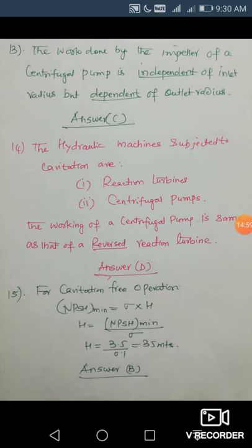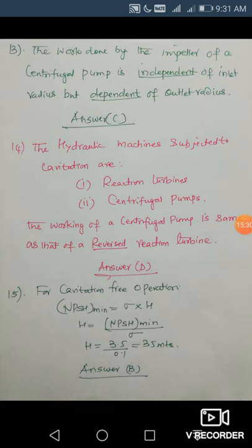For the last question: for cavitation-free operation, NPSH_min = σ × H, where σ is Thoma's cavitation factor — named after Thoma who researched cavitation. Therefore H = NPSH_min / σ. Substituting NPSH_min = 3.5 and σ = 0.1, head H = 3.5 / 0.1 = 35 meters. Your answer is B.